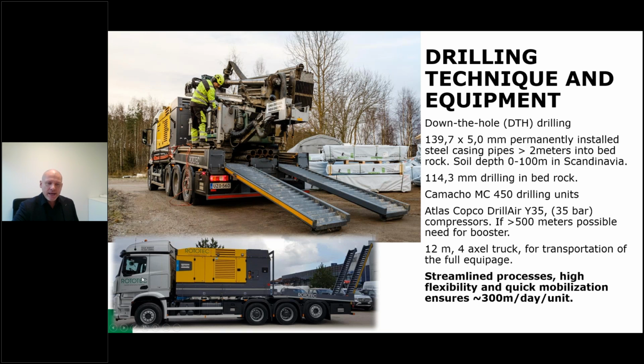So a little bit about the drilling techniques. Down the hole drilling, we use 140 millimeter and 5 millimeter permanently installed steel casing pipe, and this goes to the soil. We have a soil layer about from 0 to 100 meters in Scandinavia. So we drill with the soil drill about 2 meters into the bedrock, in which we seal the casing. We use Camacho MC 450 drilling units and Atlas compressors, 35 bar compressors, which is good enough for depths up to about 500, 600 meters. Below that, we have to use some booster compressors.